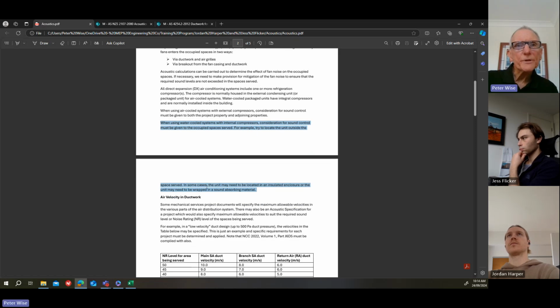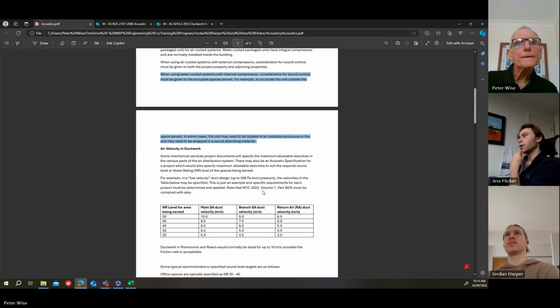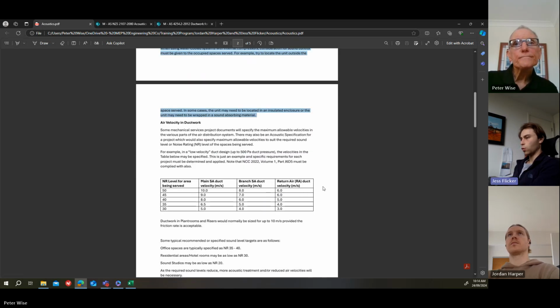That hotel that I mentioned, we had to look at wrapping the units with insulation as an option to try and take out some of that compressor noise. Is internal lining better for certain types of sound attenuation versus, say, external? With the water-cooled package units, the compressor noise is actually a breakout noise, because it's the ductwork.